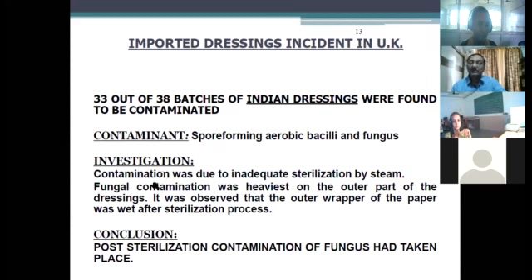Investigation was carried out, and it was found the contamination was due to inadequate sterilization by the steam. Now, the interesting point here is that these surgical dressings are sterilized by autoclaving. When we do autoclaving, steam comes in contact with this material, and therefore some water vapor is absorbed. If you do not remove that water vapor from the covers of these surgical dressings, then they will remain wet for a long period of time, and that will cause fungal growth. So the conclusion here was that post-sterilization contamination of fungus had taken place. That is where one has to be careful, that drying has to be done after the cycle is over.